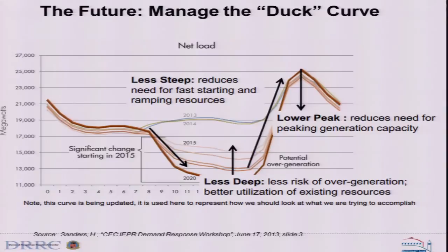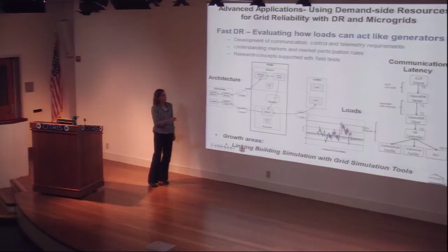This is the first project we did with PG&E, where we were asked how demand response could look like a grid-scale battery. Let me talk about this architecture for a moment. The ISO has AGC signals going to the automation server, and the same client used for critical peak pricing now gets a much faster signal and a real-time kW reading.